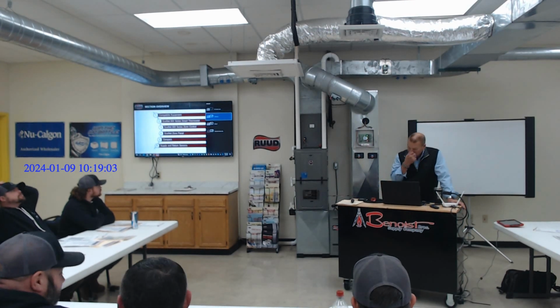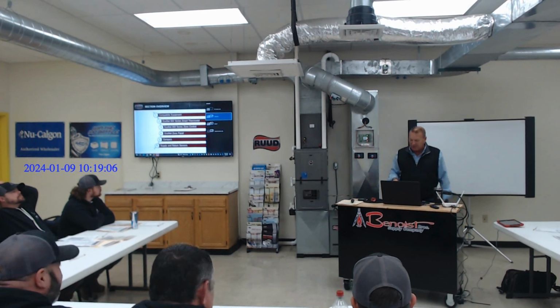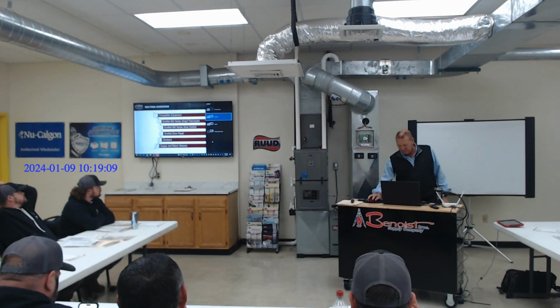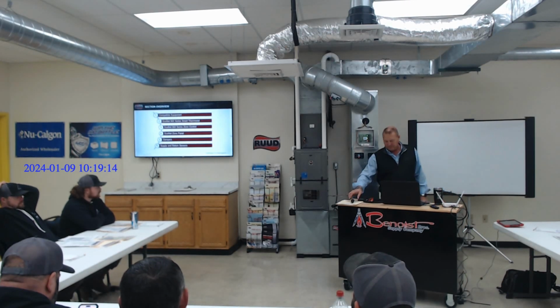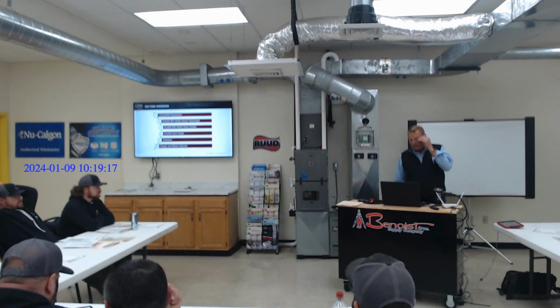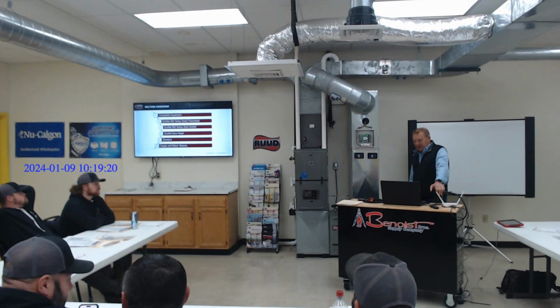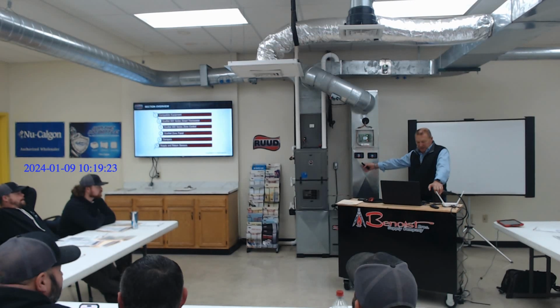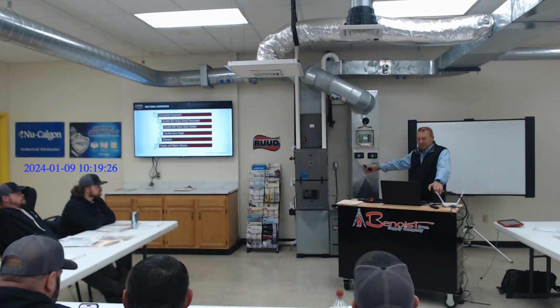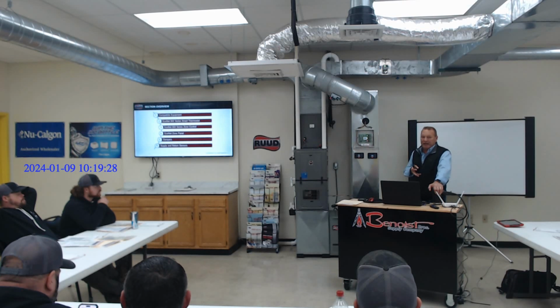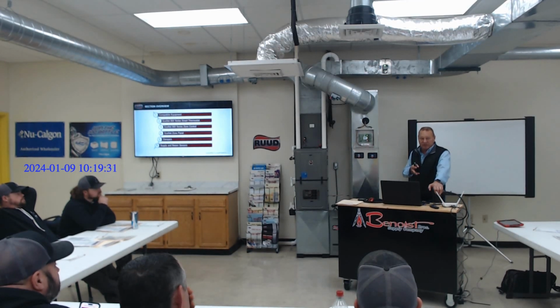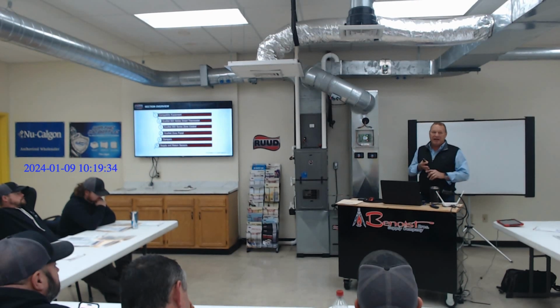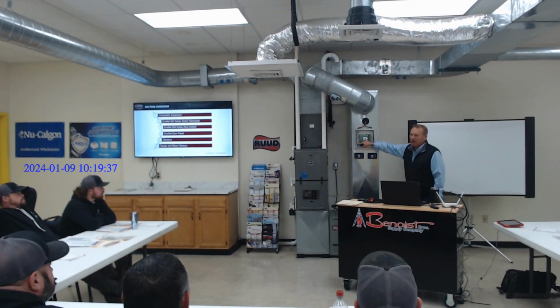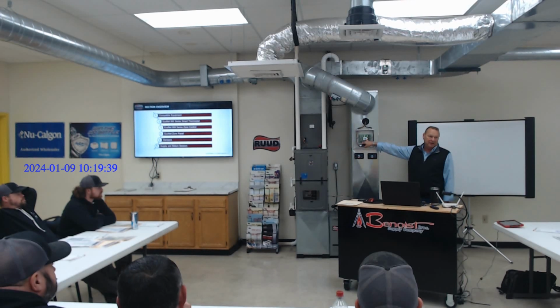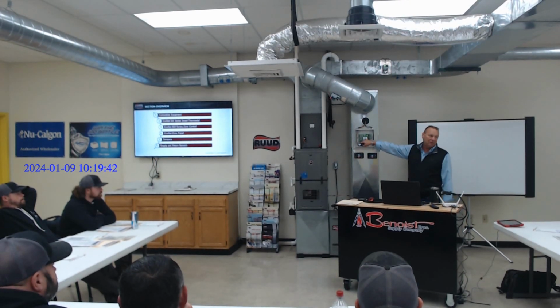Confirming that, but man, okay, first of all, we want compatible equipment. Go away. You're going to use the 800 series ECONET. You're going to need the ECONET zoning panel. You're going to need the ECONET dampers and supply and return sensors. Ruud is using EWC. They're partnered with EWC. But keep in mind that that EWC control board we have right here is a communicating board. It is not a regular zoning panel.